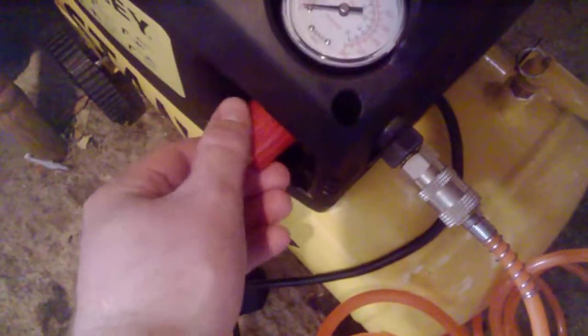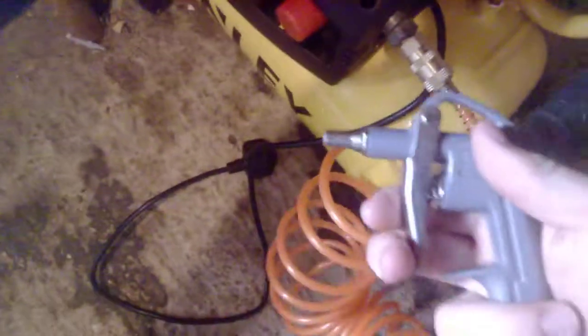But also, if you were to tighten or loosen it until the needle, let's say, got to 60 PSI—so I've tightened or loosened that valve until that needle has hit 60 PSI right there—that then ensures that the air comes out at the end is 60 PSI.